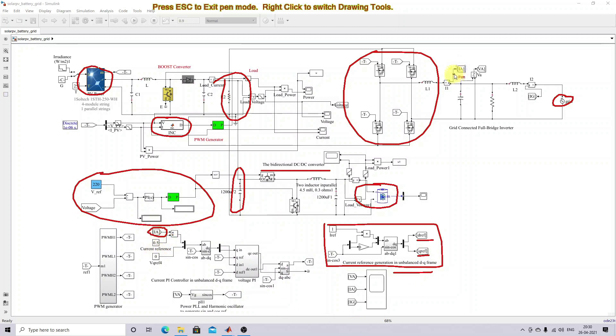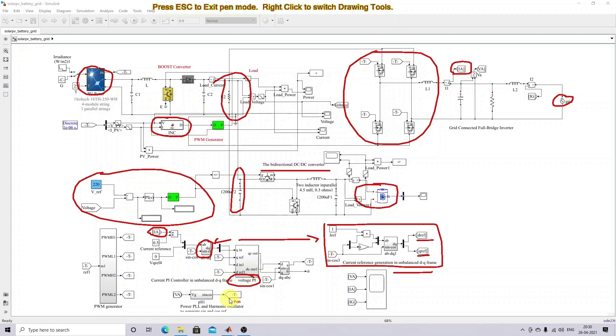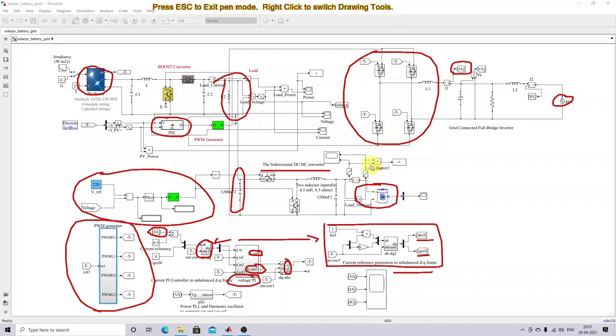The actual current of the inverter is measured, and from it we generate the actual DQ current. This DQ current is compared with the reference DQ values and processed via a PI controller, which generates the reference DQ signal. This is then converted into ABC quantities, and that control signal is used for generating the PWM pulses to control the inverter.